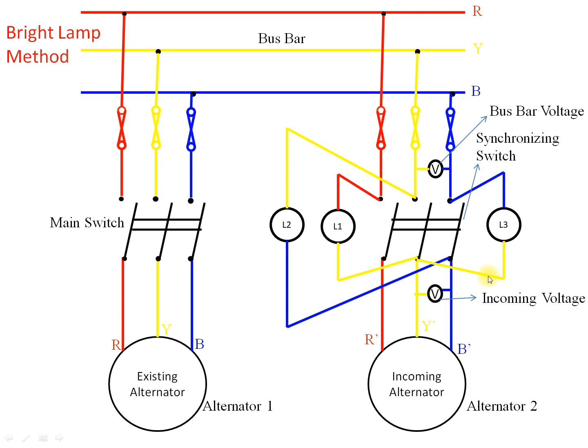If the phase sequence is not the same, then the lamps will toggle uniformly. They will first become very bright, because V1 and V2 add up and the voltage is squared, so the lamps glow very brightly. That brightening and darkening will toggle in each other in a uniform manner if the phase sequence is not the same. First L2 will glow bright, and L1 and L3 follow less bright, and then go dark. If L2 first glows brighter, and next L1 glows brighter, and L3 glows next, then we can conclude that the phase sequence is not the same.